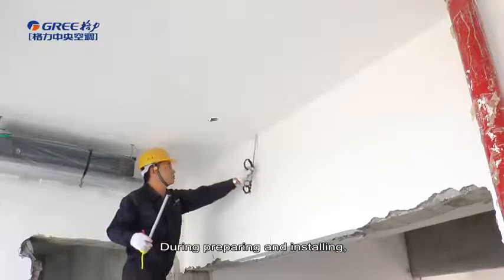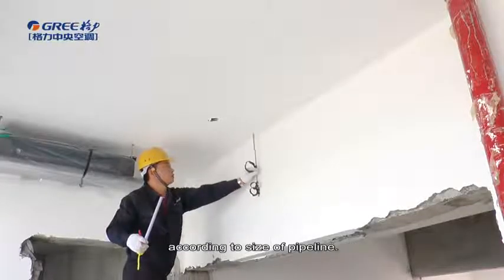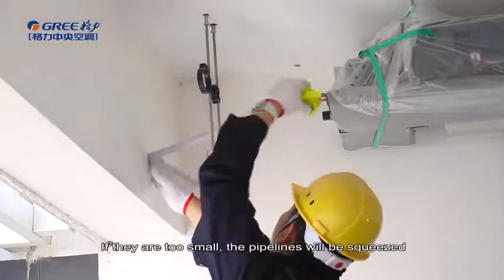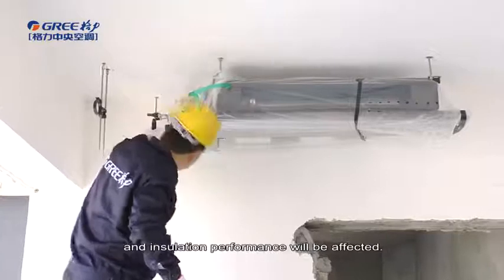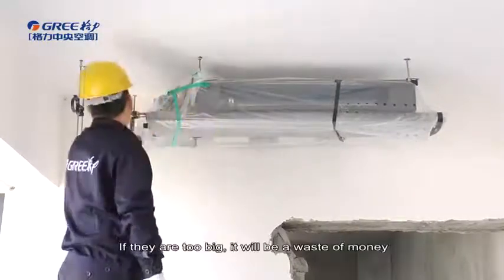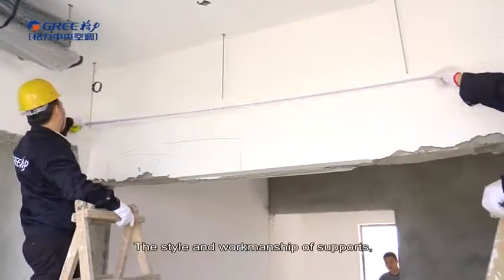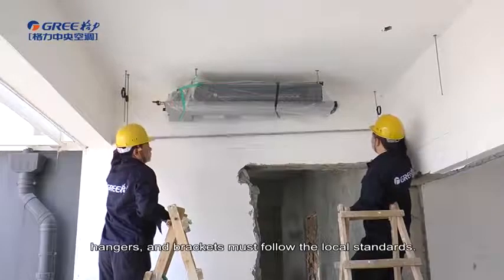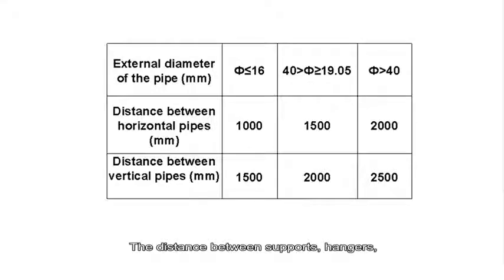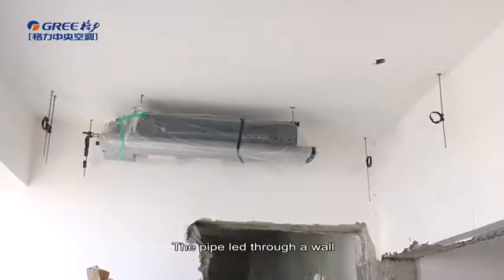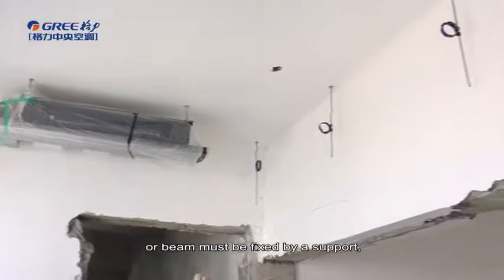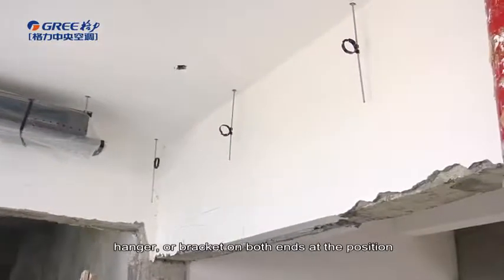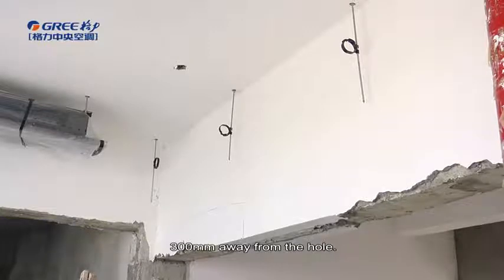During preparing and installing, choose the corresponding specification according to size of pipeline. If they are too small, the pipeline will be squeezed and installation performance will be affected. If they are too big, it will be a waste of money and the pipeline cannot be fixed properly, which may cause vibration. The style and workmanship of supports, hanger, and brackets must follow the local standards. The distance between supports, hangers, and brackets is as shown in the diagram. The pipe led through a wall or beam must be fixed by a support, hanger, or bracket on both ends at a position 300 mm away from the hole.